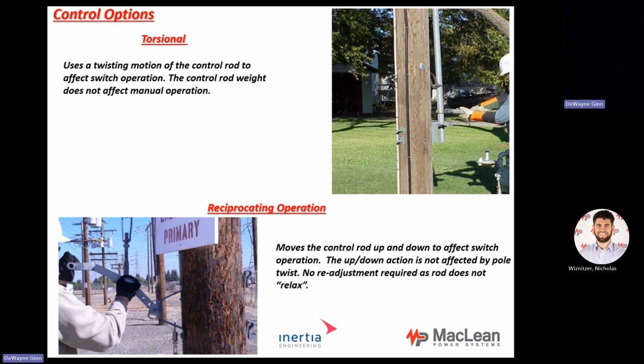It's also that wood poles now are not cured like they used to be. So as they sit in the field, they'll start twisting. And if I have a torsional, it starts twisting that pole and puts it in a bind, and I can't operate my switch. So that's a situation where torsional is not a good value, although historically it's been in the field forever on switch controls. We can do torsional on all switches except for our phase over phase. So if a customer wanted torsional, we can do it.